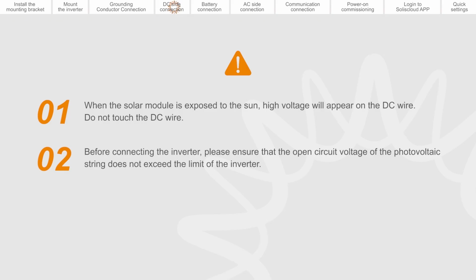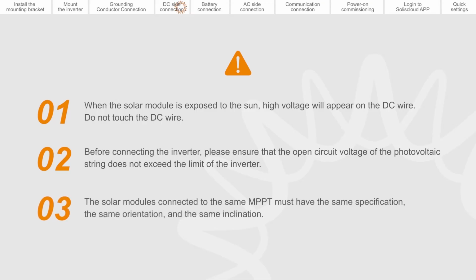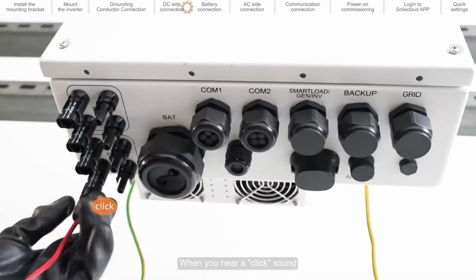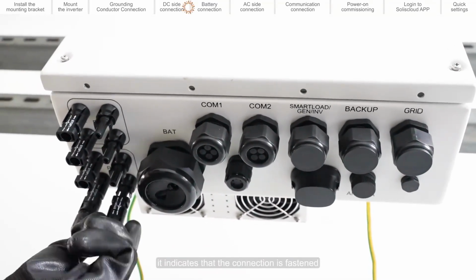Before connecting the inverter, please ensure that the open circuit voltage of the photovoltaic string does not exceed the limit of the inverter. The solar modules connected to the same MPPT must have the same specification, the same orientation, and the same inclination. When you hear a click sound, it indicates that the connection is fastened.